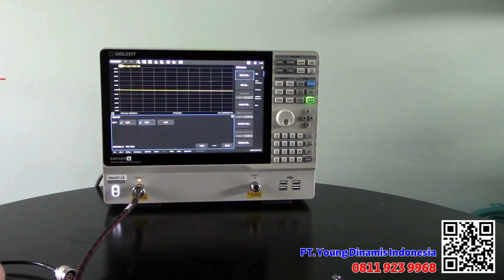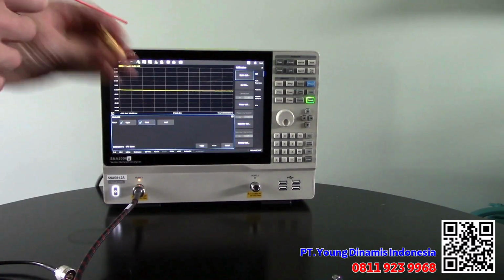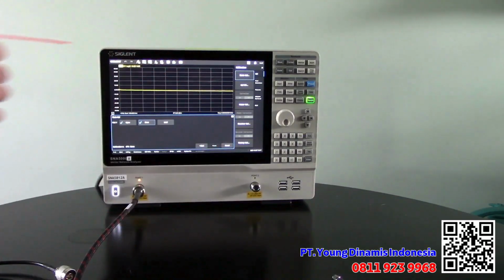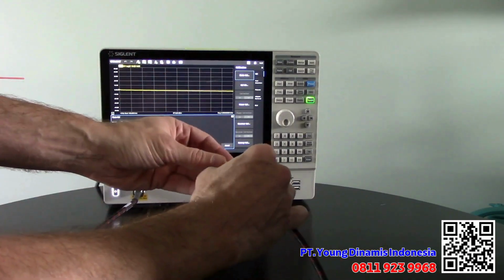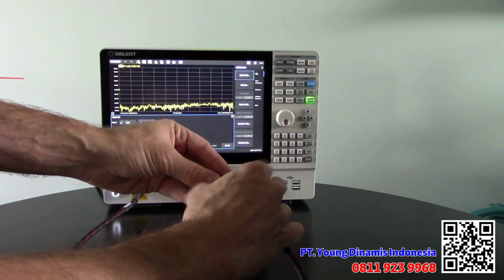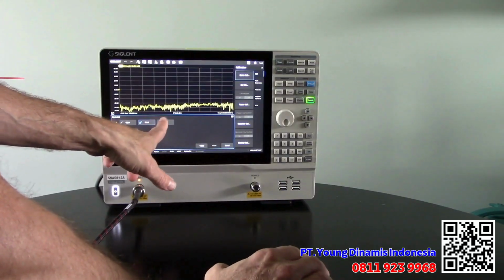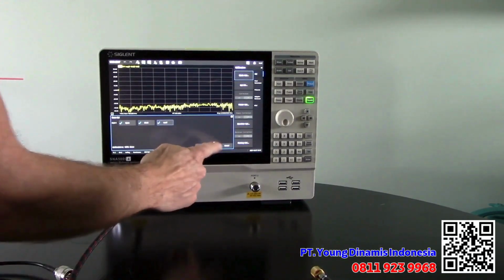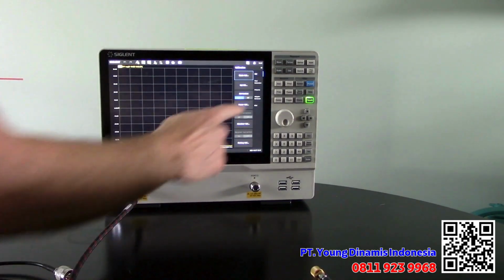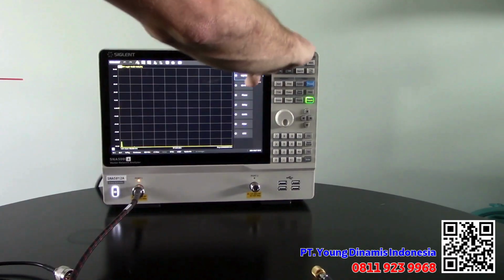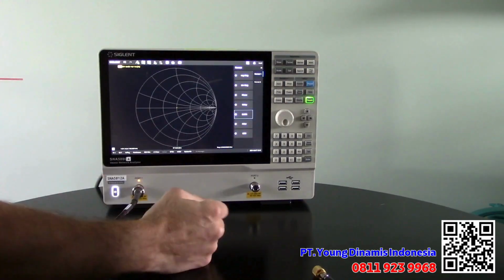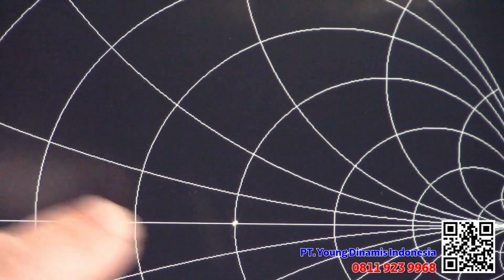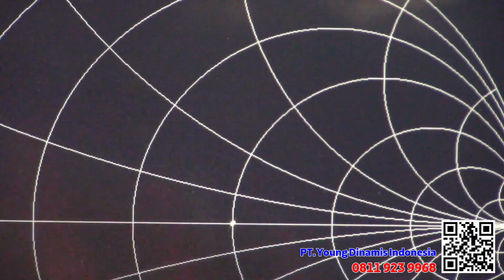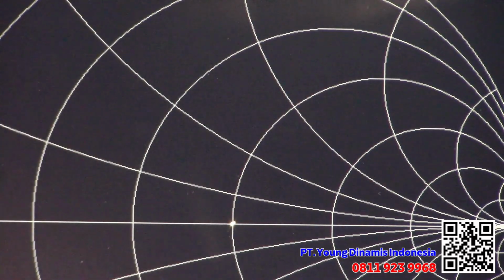And now we're going to remove that and replace it with the load. This is a 50 ohm load, which matches the characteristic impedance of the vector network analyzer input. Again, we're going to tighten the barrel, and you'll see that S11, or the reflected value, is going to change there. We're going to calibrate to that load. Once that's complete, we will accept the calibration state, and we will now switch the view over to the Smith chart and complex impedance with the Smith chart S11. And you'll see the characteristic impedance is this little yellow dot in the center with a 50 ohm load, and that is a very good calibration. You'll see as we shake the cable, that is not changing at all. And this is a sweep over 8.5 gigs.